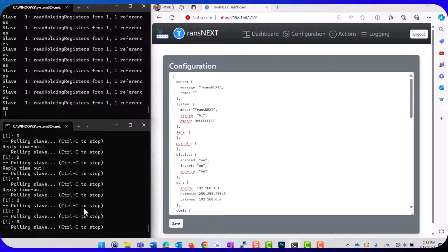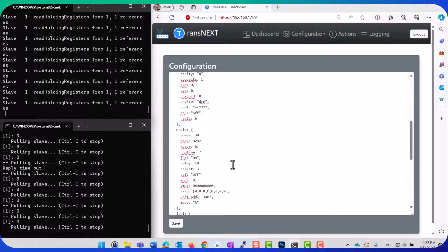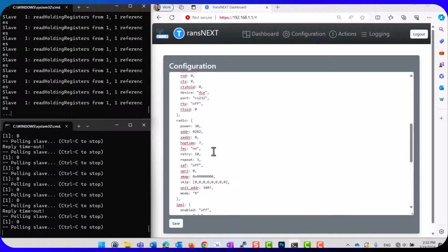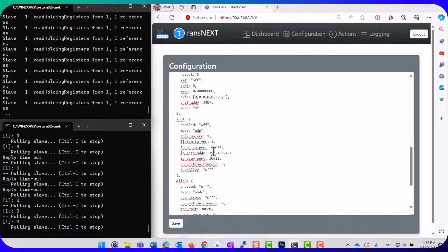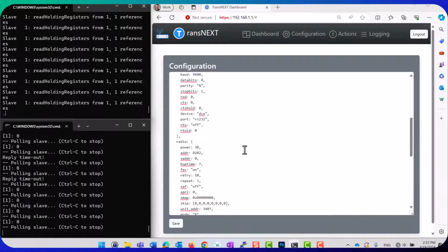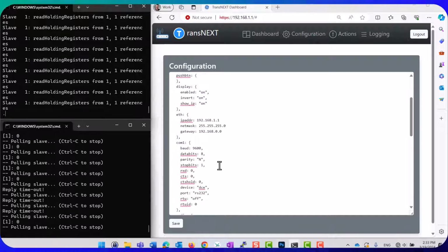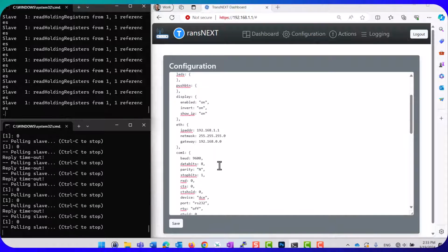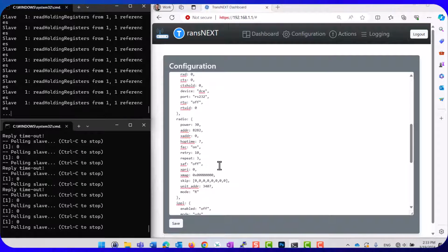Now we are having some timeouts on these polls, which is kind of interesting. I'd be curious to see in real time what we can do to potentially improve that. So let's look here to see what kind of buffers we have access to, and if there's anything we can tweak on the radio. We are doing 9600, 8N1. Not seeing a lot here, so let's see, we've got hop time is 7.